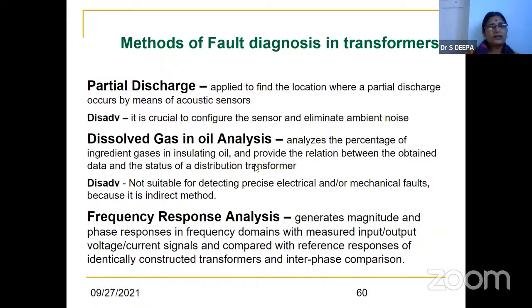So, dissolved gas in oil analysis. The transformer will be filled with oil for cooling purposes, but depending on the temperature, it will liberate different gases. Gas sensors will be used to find what level of fault it is. That is the analysis: the percentage of ingredient gases in insulating oil, and it provides the relation between the obtained data and the status of the distribution transformer. So it is not suitable for detecting precise electrical or mechanical faults because it is an indirect method.